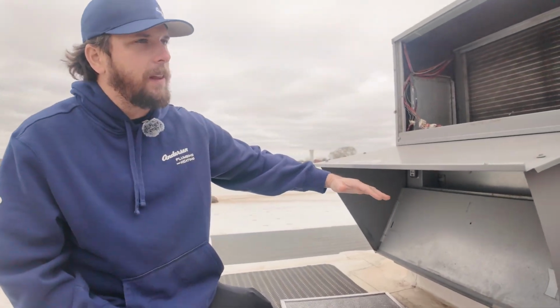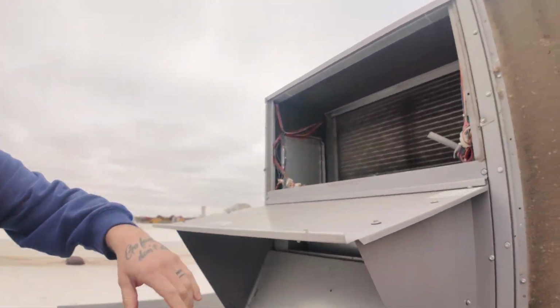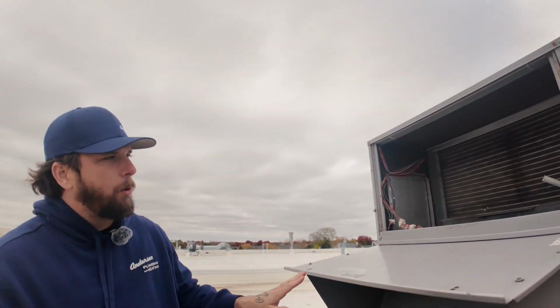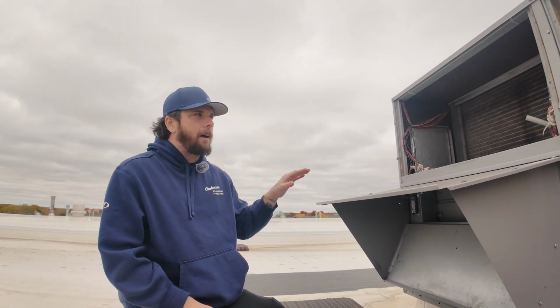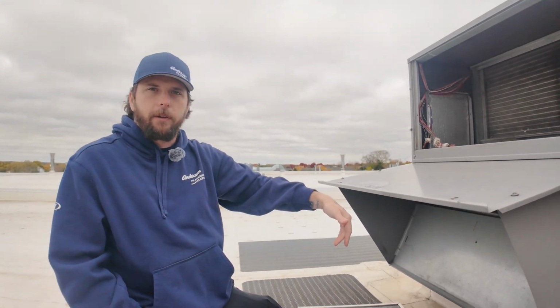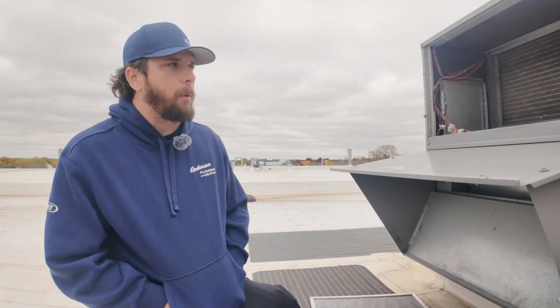So what an economizer will do is it'll open up these flaps, it'll leave the air conditioning off, and it will pull that cold outside air in through the evaporator coil and then push it down into the building. So it's a way that you can achieve air conditioning without really running the AC. You're also saving a ton of power doing that, because all you're running is the blower at that point.